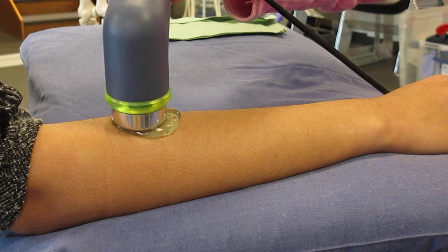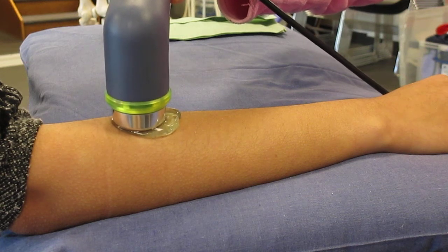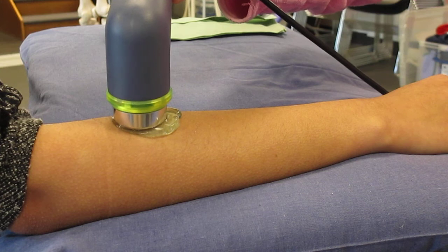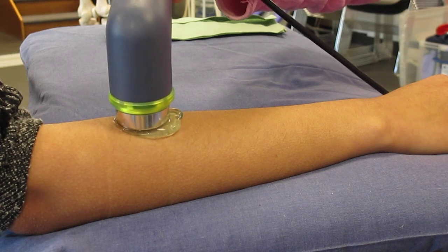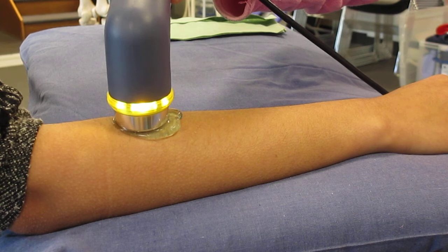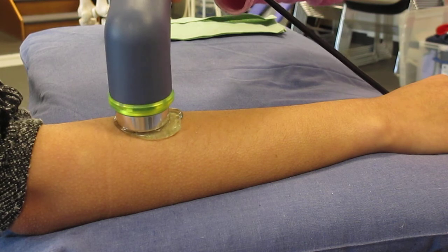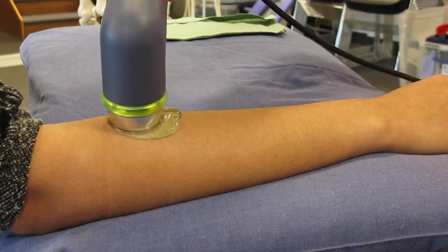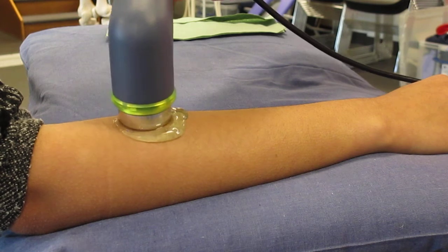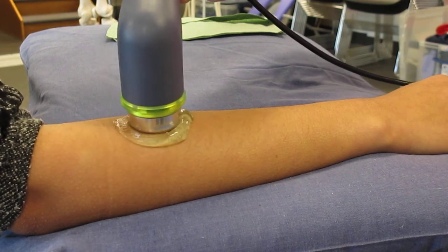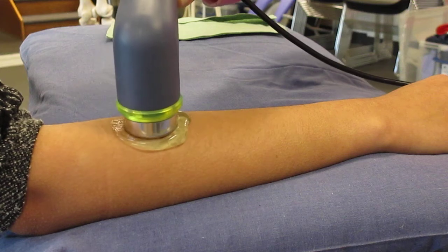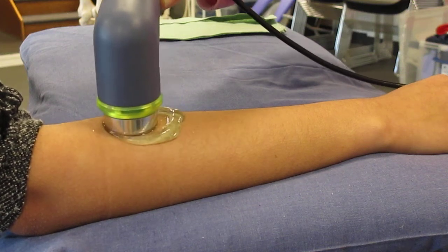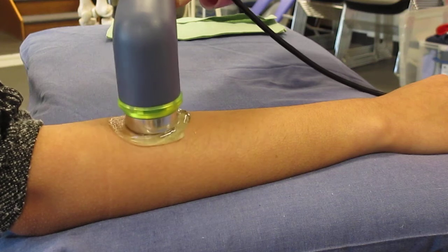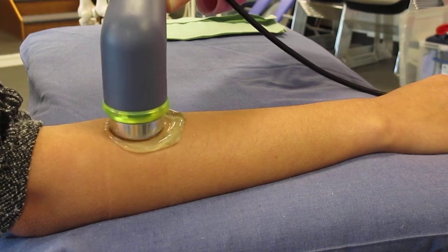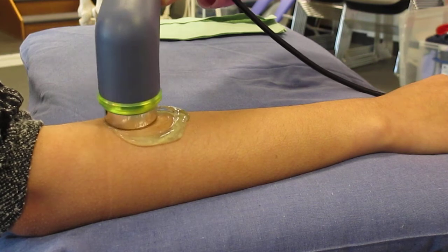So I've got 3 megahertz and I've got it pulsed, and then I'm going to turn it to a treatment time of 1 minute and turn up the intensity to about 0.3 of a watt per centimeter squared for an acute lesion. And then what you need to do while you're doing the treatment is make sure that you're continuously moving the head to avoid a standing wave forming. So you carry on moving the head around the area that you're treating until your buzzer goes off with the treatment time.